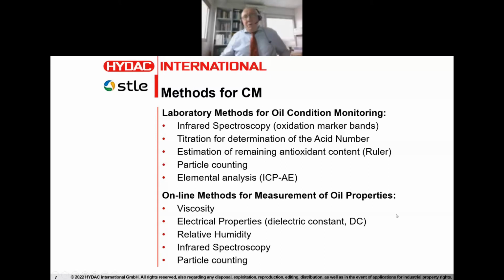Then the online methods for measurement of oil properties, like I mentioned before and will go over again: viscosity, electrical properties, dielectric constant, conductivity, relative humidity, infrared spectroscopy. In a very curious development, long ago at Pacific Northwest National Labs, they had a non-dispersive infrared spectrometer where they basically used filters, and they mounted these different filters onto a CD. This CD would rotate into a particular position with a different filter, and you would be able to interrogate certain very well-defined regions of the infrared spectrum. For example, looking at the carbonyl at 1700 wave numbers would tell you whether the oil is undergoing oxidation or not. And of course, particle counting, which was one of the earliest analytical procedures adapted for online use.